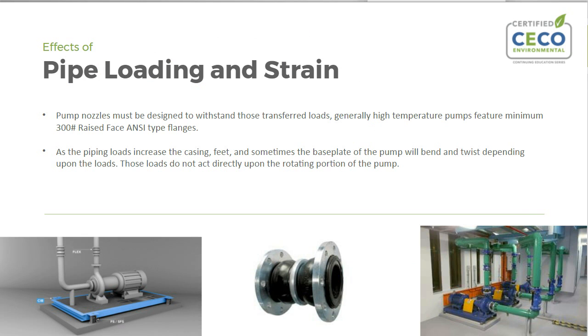Another effect is external effects on the pump itself. The external effects, it's not only the pump that is increasing in temperature. Everything is increasing in temperature. As you heat up your system, your piping, your valves, all your fittings, everything else is increasing in temperature. In most cases, these are all insulated items, so they're holding on to that temperature even after the system is shut down.